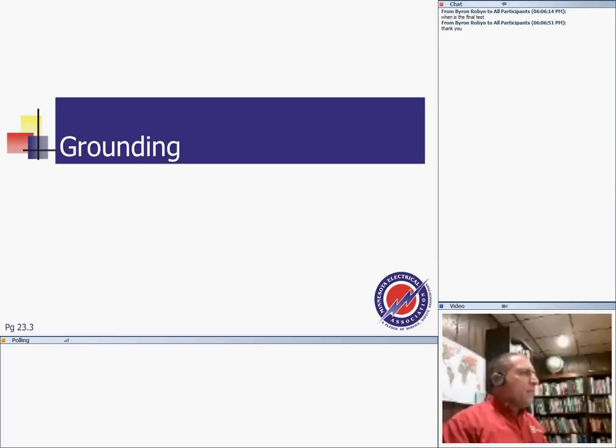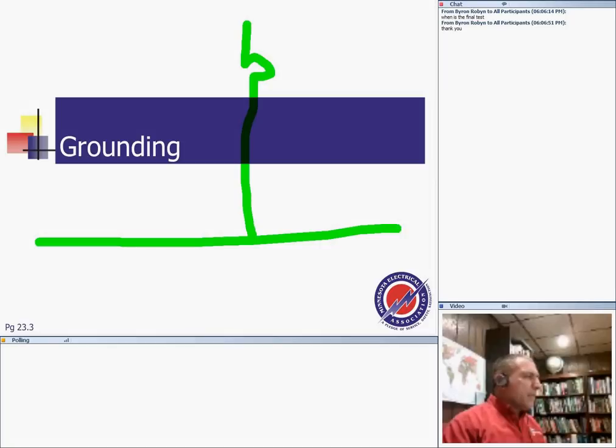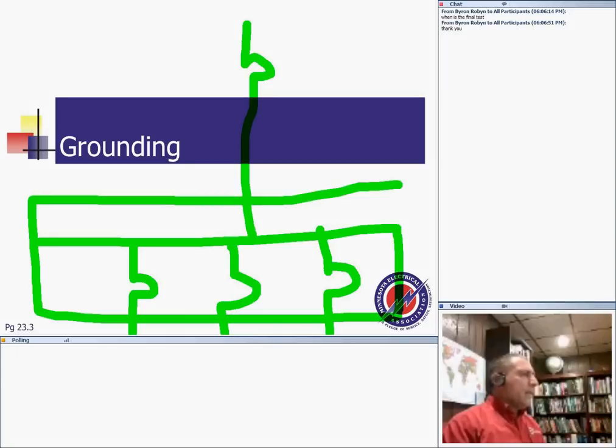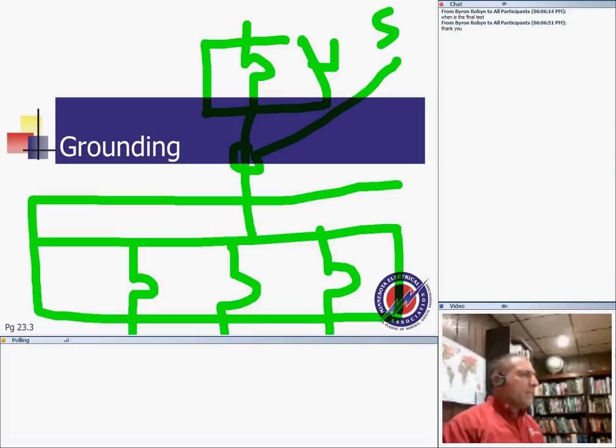Same thing, guys, we did the service. I want to quickly remind you, we did the service. You can also apply the same calculation for the feeders. Here's my feeder if you have an apartment building, here's the panel at the bottom. The same calculation that we have just gone through, and here's my disconnect for this apartment directly here. The same calculation for the service can apply for all these feeders.